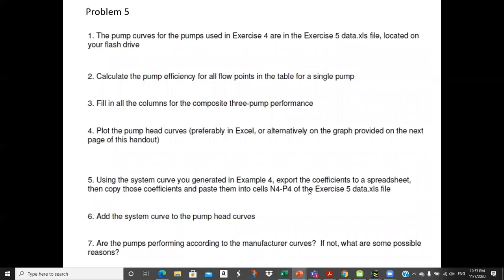Okay, so problem 5. What we're going to do here is the pump curves for the pumps used in exercise 4 are in the exercise 5 data Excel file, which I will send out to you. Well, it's not located on your flash drive, but I'll send it out. Calculate the pump efficiency for all flow points in the table for a single pump. Fill in the columns for the composite 3 pump performance. Plot the pump head curves, preferably in Excel, which is what we've done. Using the system curve you generated in example 4, and I used the one for exponent 1.9, export the coefficients to the spreadsheet, then copy these coefficients, paste them into the cells, etc.